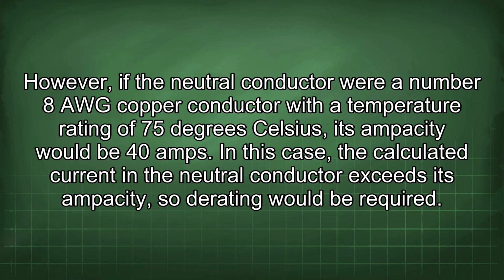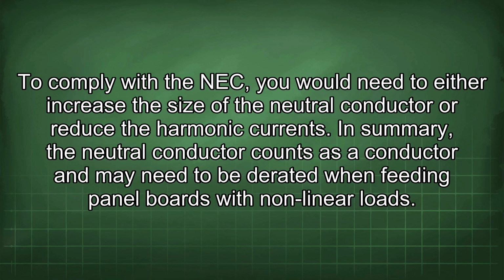However, if the neutral conductor were a number 8 AWG copper conductor with a temperature rating of 75 degrees Celsius, its ampacity would be 40 amps. In this case, the calculated current in the neutral conductor exceeds its ampacity, so derating would be required. To comply with the NEC, you would need to either increase the size of the neutral conductor or reduce the harmonic currents.